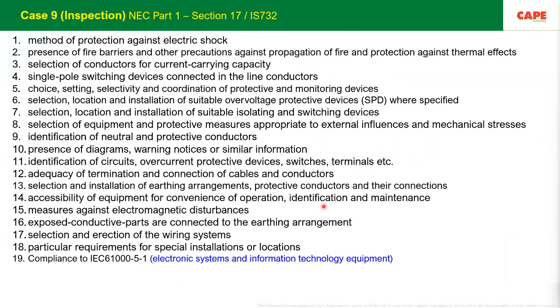The IS 732 or the BS 7671, the wiring rules of Britain, or the National Electrical Code of America, or the NFPA 70, all these standards and the Indian standard IS 732 have included serial numbers 1 to 18 as inspection points in the standard. This is globally accepted, and globally this has to be carried out. But unfortunately, this is also missing.